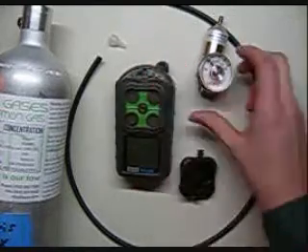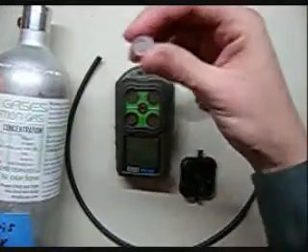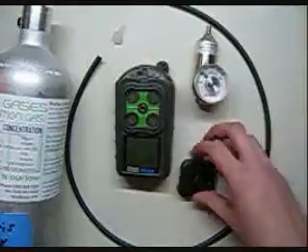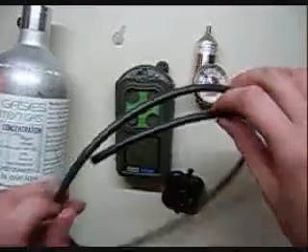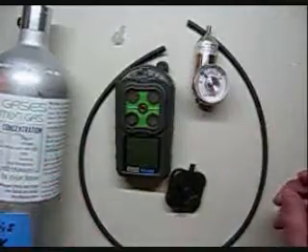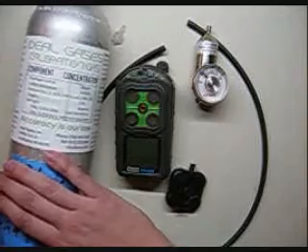We're going to need the monitor itself, a 0.25 liter per minute regulator, an adapter for the cal cup, the cal cup itself, some tubing. I prefer the Viton tubing over the Tygon and the Teflon line, and also a cylinder of calibration gas. We use the Ideal Gas brand.